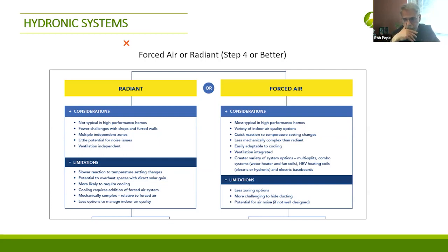Any solar gain adds to the heat coming into the building. If you have a radiant system in there, especially in the shoulder seasons, it can sense the heat coming in from solar and internal gains. It'll shut off the thermostat, but all that mass takes a long time to drop in temperature - that's the problem. You get overheated because the house is so thermally high performing.